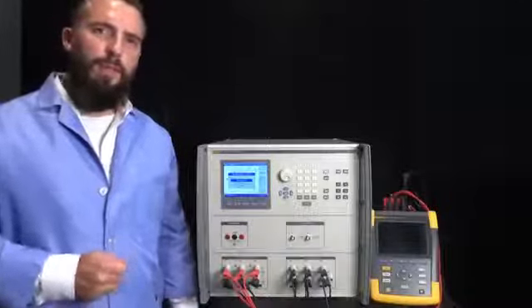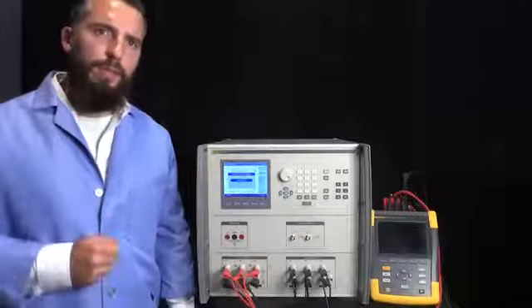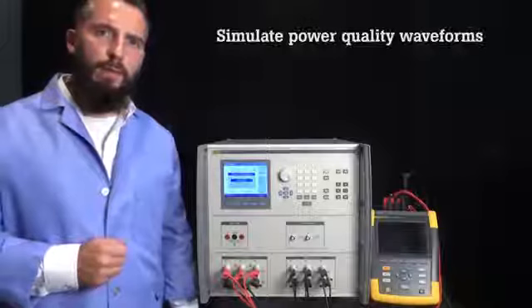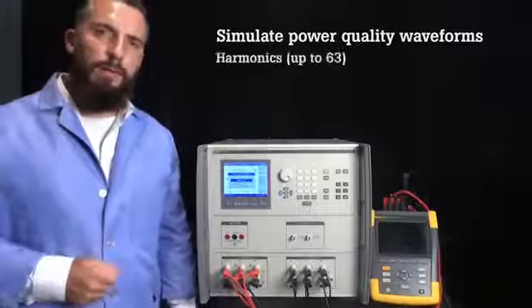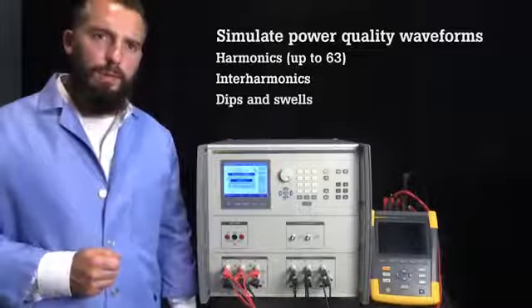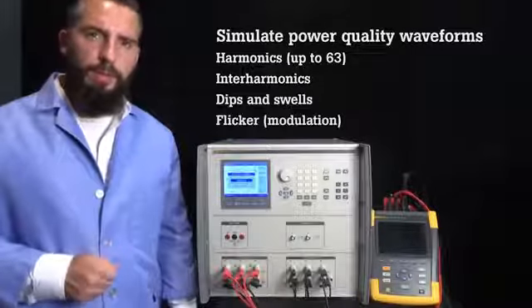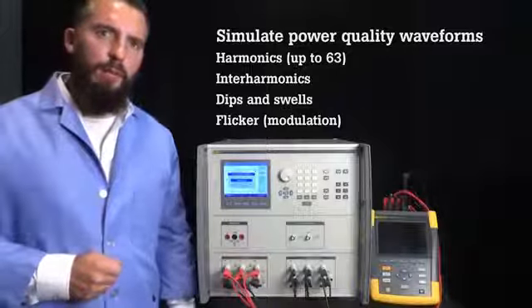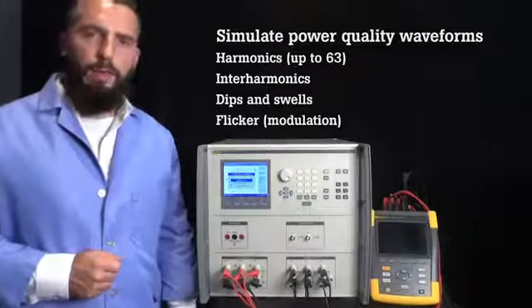The 6003A has unique advanced functions that let you change the output to accurately simulate these power quality waveforms: harmonics up to the 63rd harmonic, inter-harmonics, dips and swells, flicker, or modulation. This functionality will be covered in more detail in another video.